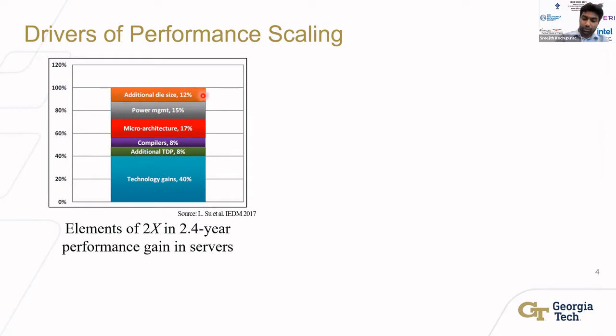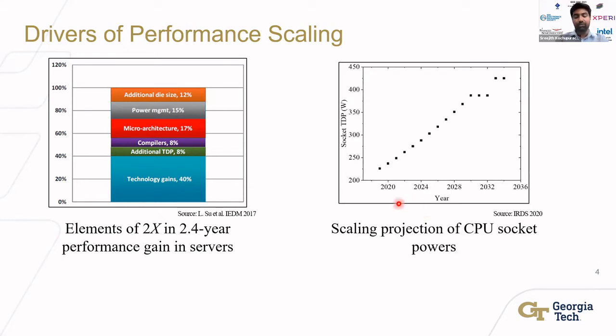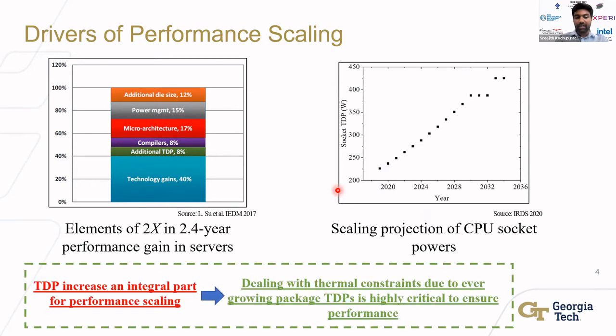A major contributor to increasing performance today is essentially packing more silicon into the package and dealing with higher TDP. Based on IRDS projections, socket TDP for server sockets is projected to increase to much higher levels in the next decade. Managing this TDP increase is integral to keeping up with performance scaling, requiring new and improved thermal management techniques.